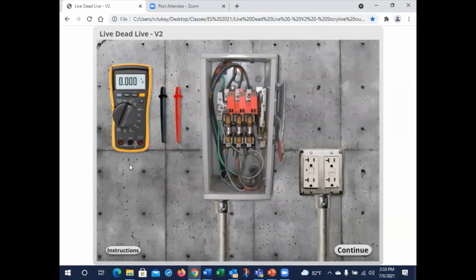And the first thing they want us to do is test this on a known voltage. Well, no issue here, right? Because we have a receptacle. But there are times when I go up to some industrial machinery that I have done the first 6 steps, and now I'm on this step, and I have shut all the voltage off because what I de-energized was the machine that I'm actually trying to verify right now. So I can purchase a voltage sourcing unit. Many manufacturers make these. They come with a magnetic strap that I could actually hang this voltage sourcing unit right on the equipment. It will give me 240 volts AC or 240 volts DC wherever I go. And that would test my meter on a known voltage.